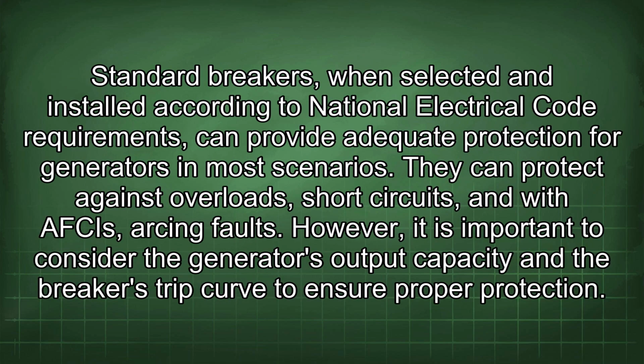Standard breakers, when selected and installed according to National Electrical Code requirements, can provide adequate protection for generators in most scenarios. They can protect against overloads, short circuits, and, with AFCIs, arcing faults. However, it is important to consider the generator's output capacity and the breaker's trip curve to ensure proper protection.